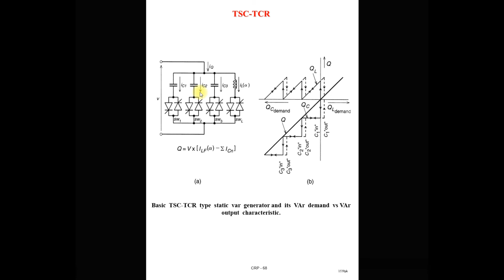Again, if you require more capacitive reactive power, between 20 to 30 MVAr leading reactive power, in that case again you turn on this third branch of the capacitor. So a total of 3 branches provide the 30 MVAr reactive power, but our requirement is between 20 to 30. So again shift the firing angle of this TCR from 90 to 0. At alpha 0 degree, this TCR absorbs the 10 MVAr reactive power, so 30 minus 10 gives 20 MVAr at this point.